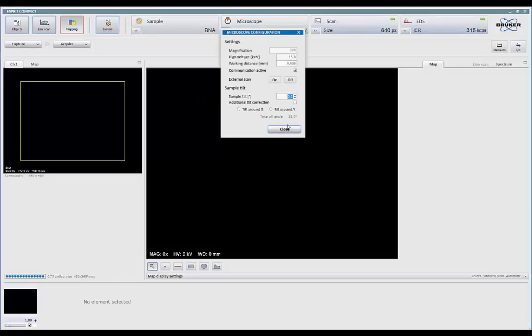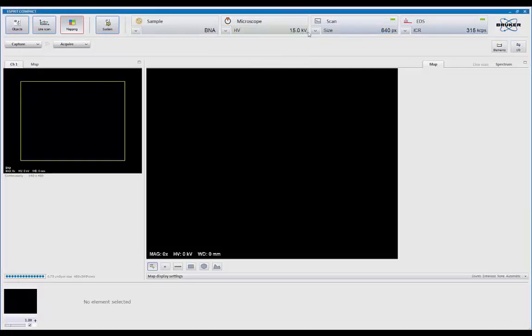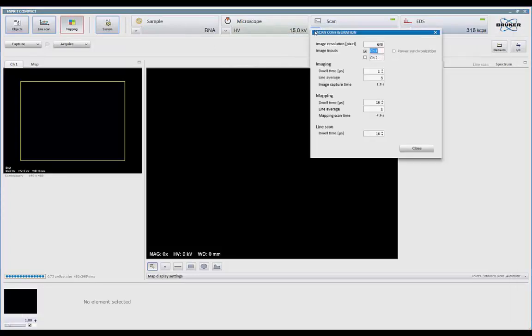We are in constant communication with the microscope, so every time we start an acquisition, we get the latest information from the microscope and save it with the data. Scan controls for the digital beam. We can collect images from 100 on up to 4096 pixel resolution, any size you wish.